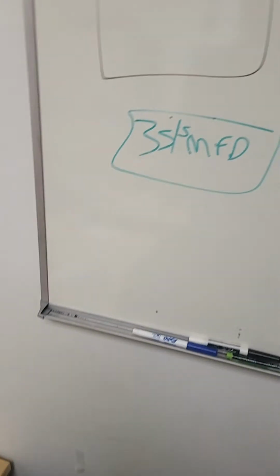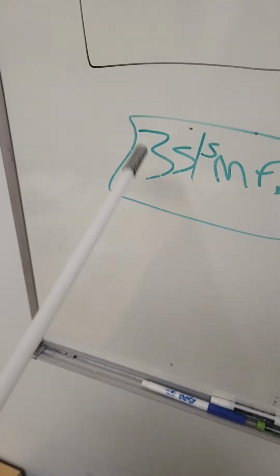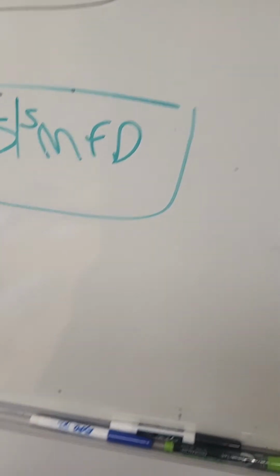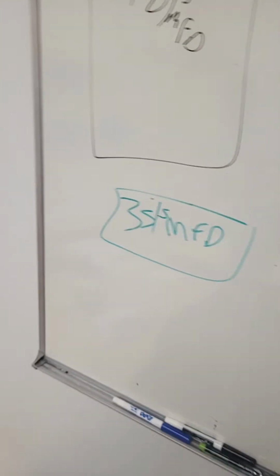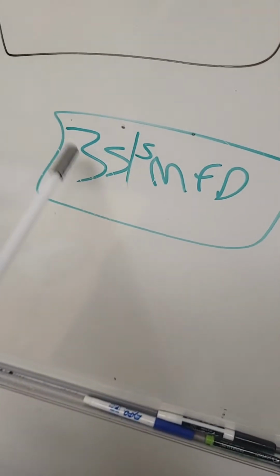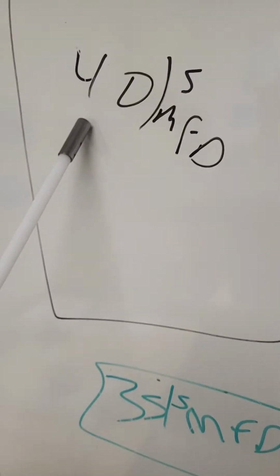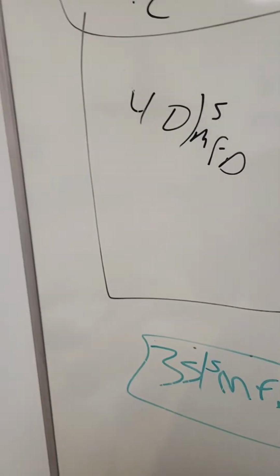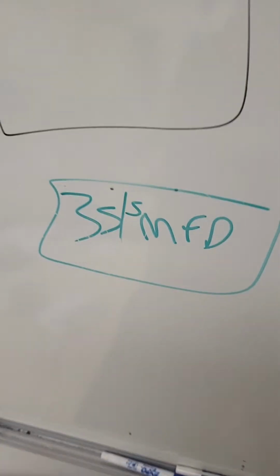I always say in a pinch, and this is only for when you cannot find the same size cap, try to get the same size within 24 hours. But if you can't find that same size cap, you could temporarily put in one that's within 5 microfarads of whatever you took out.